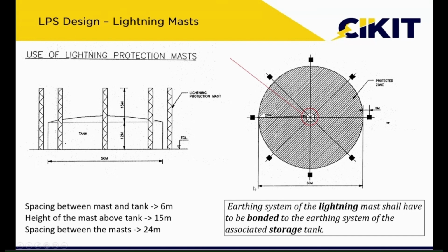Here, in order to avoid dangerous flashovers, we have to maintain a spacing of around 6 meters between the tank body and the lightning mast. If you observe here, they have maintained this 6 meter spacing, that is, between the tank wall and the lightning mast. In order to provide protection similar to the 6 meter height air terminals on the wall, we have to provide 15 meters height. So the height of the mast has to be 15 meters above the tank wall.